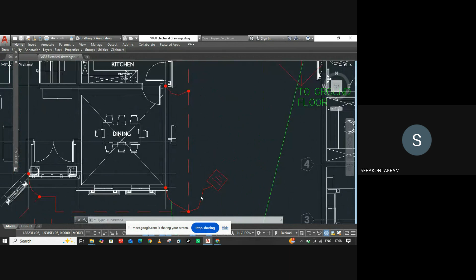So this dotted line represents our ground ring. It's made of a single core sheathed cable, which is really offset one meter away from the building, and it's buried about 750 millimeters below the pavement. So I want you also to research more about earthing, why those distances, and the different types of earthing.